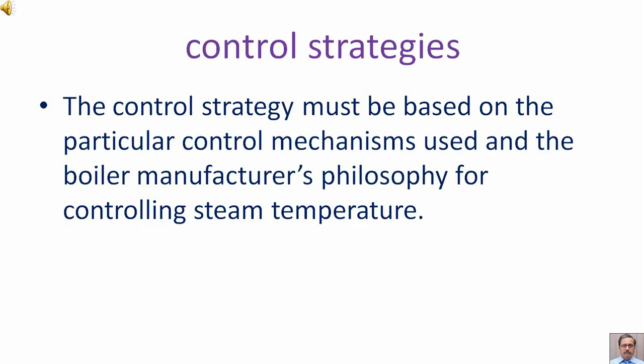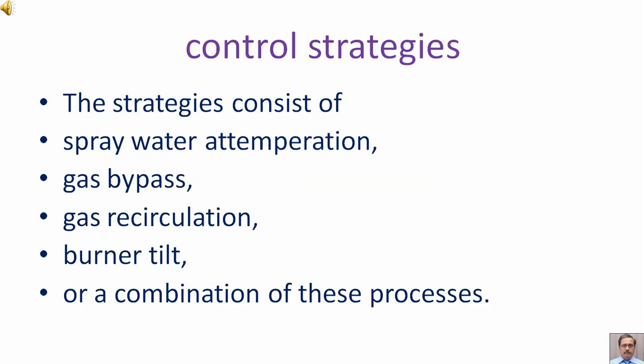The control strategy must be based on the particular control mechanisms used and the boiler manufacturer's philosophy for controlling steam temperature. The strategies consist of spray water attemperation, gas bypass, gas recirculation, burner tilt, or a combination of these processes.